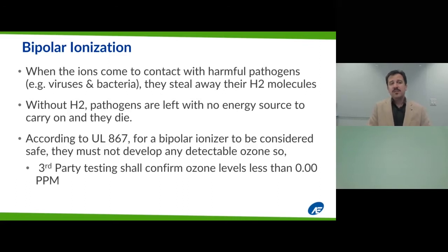Now, there could potentially be a problem with these ionizers, and that's that they can potentially create ozone, which we know is not good for indoor climates. For an ionizer to be considered safe and used by an HVAC engineer, it must not develop any detectable ozone. So third-party testing shall confirm ozone levels of less than 0.00 ppm. That means if we get 0.003 ppm, our ionizers pass that threshold. However, if we get 0.005 ppm, basically that's no good. This is great, right? Shall we use them? We can use them.